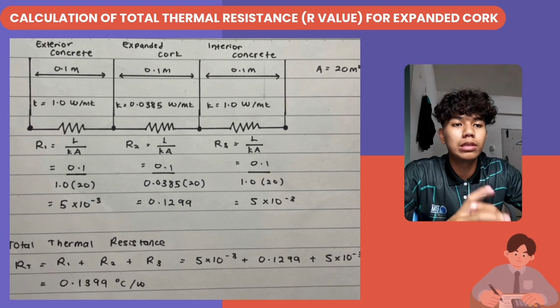For concrete, since it's the same material, we use the same formula and same data, which is thickness divided by thermal conductivity times area. So we put all the data together: 0.1 divided by 1.0 times 20. And for expanded cork: 0.1 for the thickness, over 0.0385 for thermal conductivity, times 20, which is the area.